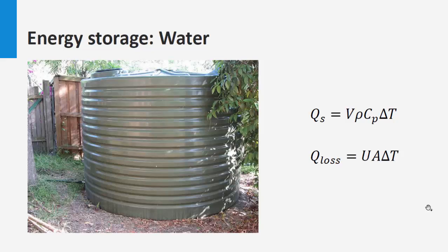The heat loss of the tank can be determined by Q loss = U A ΔT, where A is the outside area of the tank and U is the global heat exchange coefficient. The value of U gives the quality of insulation and usually varies between 2 and 10 watt per Kelvin. The U is also a function of the different media between which the heat exchange takes place.